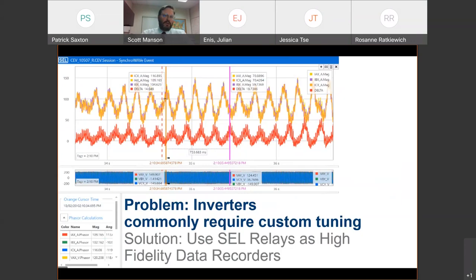Let me give you another point of fact. When you change a protective relay's settings in the field, it is required that you test it thoroughly. You bring test kits, you bring technicians. There are entire companies that independently audit and test protective relays. Ask you a question. Do you have that testing regimen and those companies in place to test your inverters? Nope. Too much trust, folks. We can't trust that which we don't control. Trust but verify. We use relays to verify.